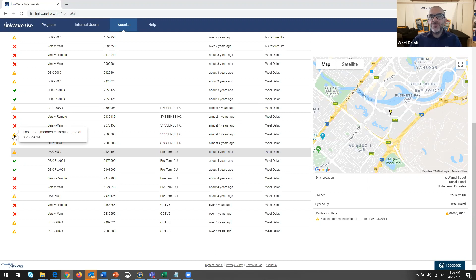But if I click on the one that Werner was using, I can see the calibration was done on 22 November 2019. So Werner is now using a DSX 8000 that is calibrated, and due for calibration in about 6 months, and then he's good. So on the field, he's good to go. But for anything I see a warning on, I can check on it.